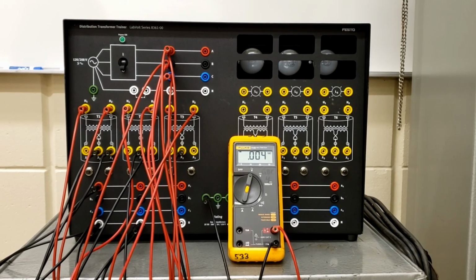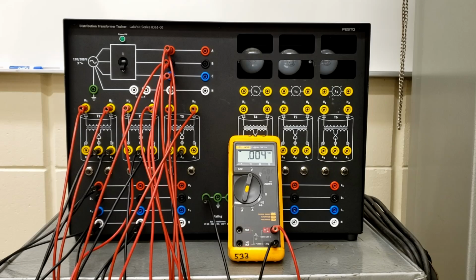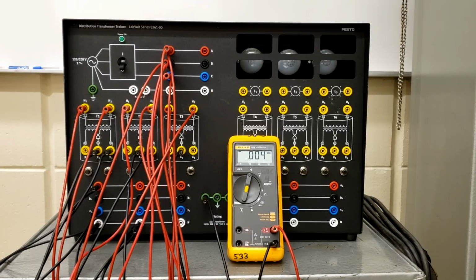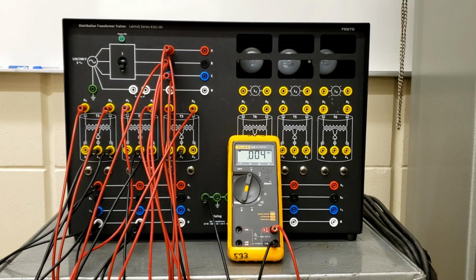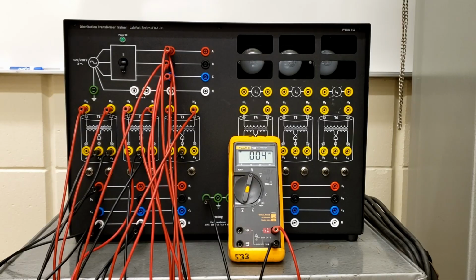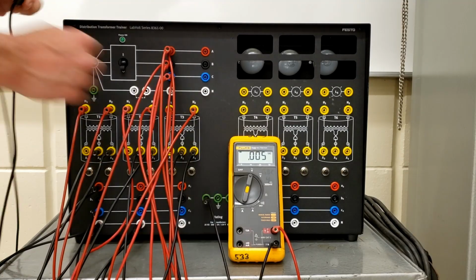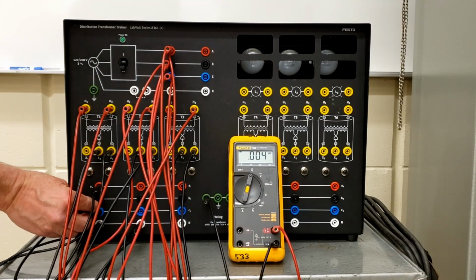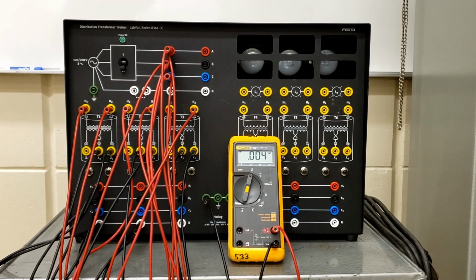On transformer 1, H1 is fed by the A phase, and X1 is feeding the A phase on the secondary. On the third transformer, H1 is being fed by B, so X1 should be going to the B phase. Our final connection for X1 is going to the B phase.